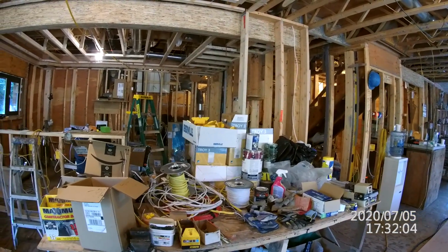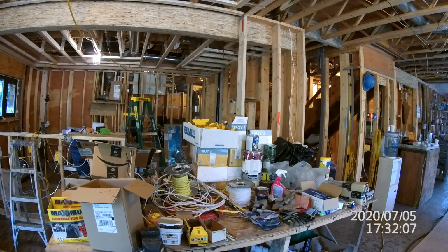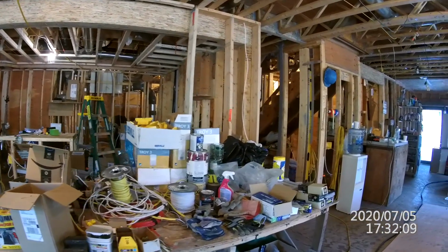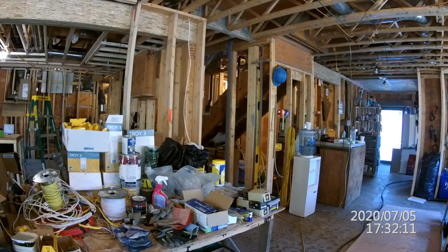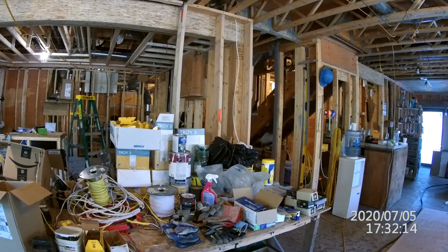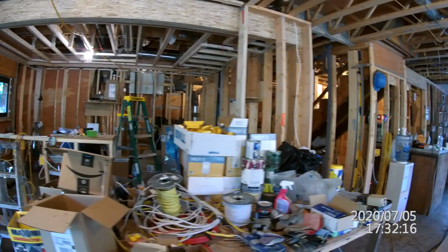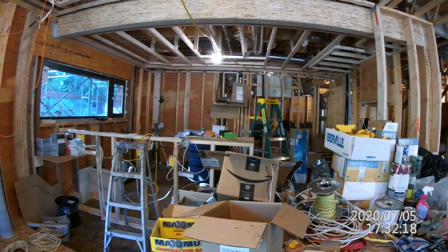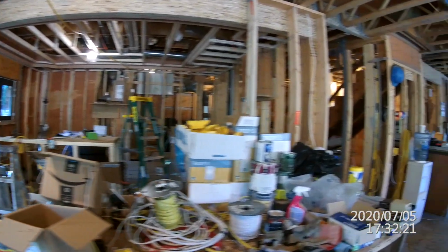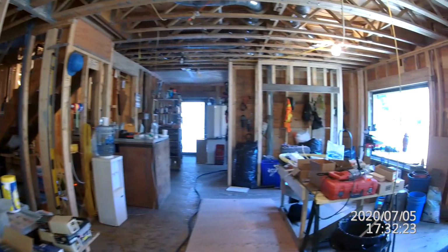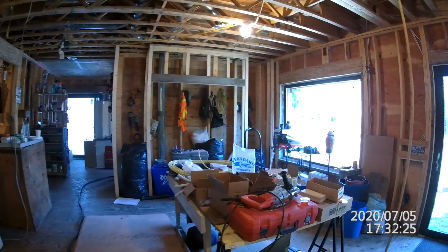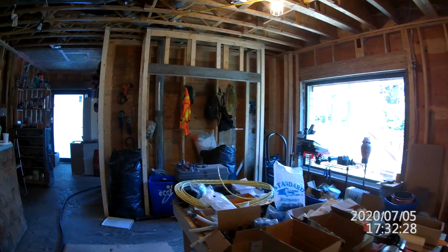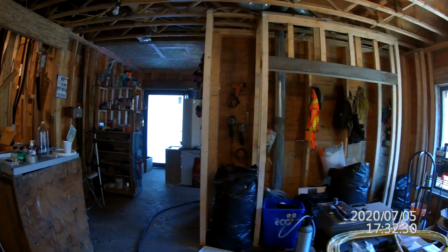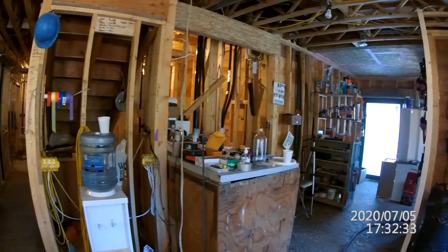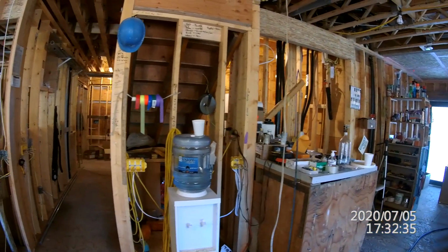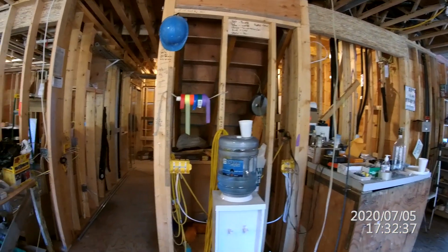Because I'm running centralized DC, I had a big learning curve on what's required to send DC throughout the house. I'm used to just doing a small kitchen circuit, where basically the rule is if it's under 96 watts, it's not that important by electrical code. Once you get above that, you start getting into what are called class 2 and class 1 electrical circuits.